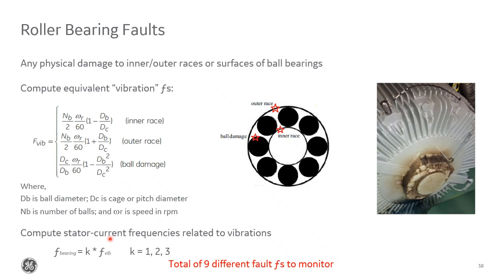So here's one thing we've updated in firmware version 2.7. In the older firmware, if you have an existing installation, we would add these vibration frequencies to the line current frequency to get the additive effect of it. The changes in our algorithm, which we'll see in a moment, essentially normalize the input signal that we're processing to the line current, so we no longer need to incorporate that factor. So we simply find the vibration frequencies, and now we just apply this K factor to them, which is equal to 1, 2, or 3, and is simply to account for subharmonics of these vibrations. So this is all we do in the newer firmware, which is a lot simpler.